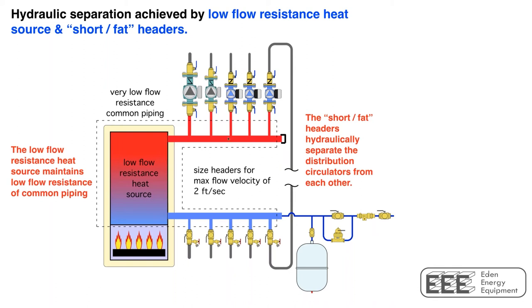When we talk about headers, I like to use the term 'short and fat' with regard to good design. Generously size your headers and keep them as short as practical — we don't want any more pressure drop along the length of the header than necessary. When we combine short fat headers with any heat source, remember it doesn't matter what's generating the heat — burning fossil fuel, a compressor, anything. What matters is the hydraulic characteristics of moving flow through that heat source, and anything manufacturers do to keep that low is beneficial in terms of providing hydraulic separation.